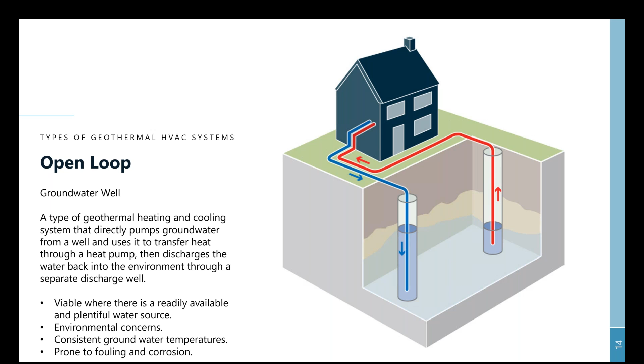We get fairly consistent groundwater temperatures with this type of system because, again, you're usually digging a well relatively deep where the groundwater temperature is going to be very stable. As it is sort of brackish water that you're pulling directly out of the ground, these types of systems are prone to fouling and corrosion on the indoor equipment. So filtration for a system like this is really critical.